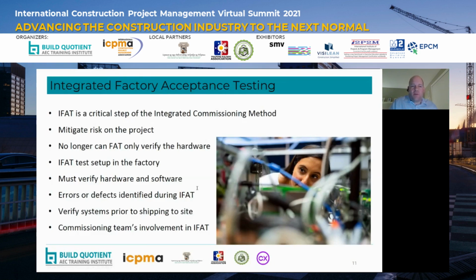Typically in the past, 10 or 20 years ago, the focus would have been on factory acceptance testing of the hardware only—verifying the cubicle has all the PLCs installed correctly and all the wiring is correct, then shipping it to site. But that no longer works for integrated digital systems. The critical aspect is that IFAT must include both hardware and software, which requires the software design to be available much earlier, but it's critical that both are tested in the factory before shipping to site.